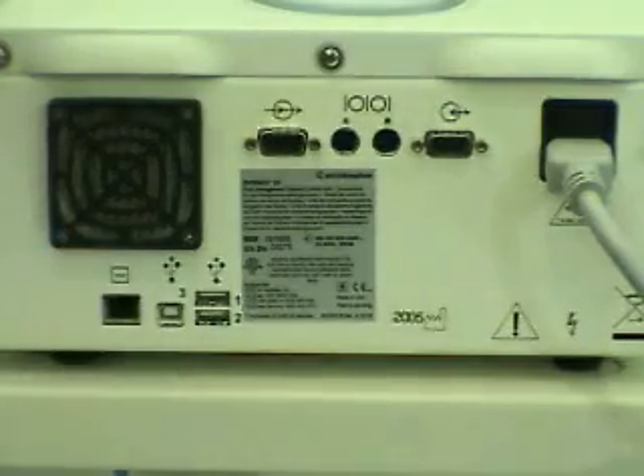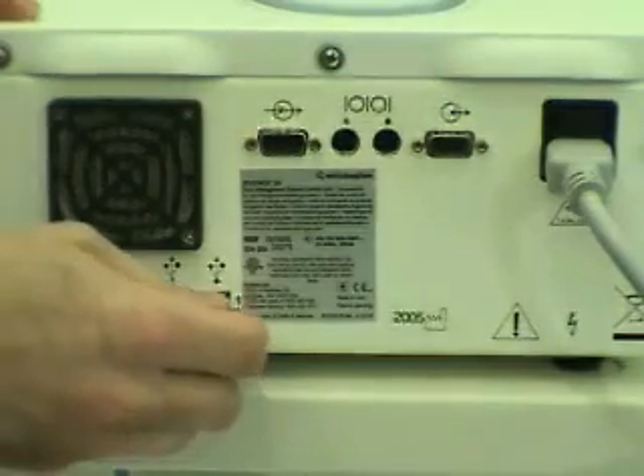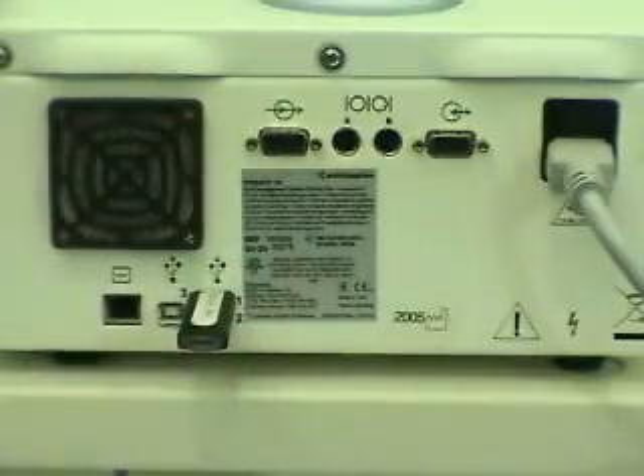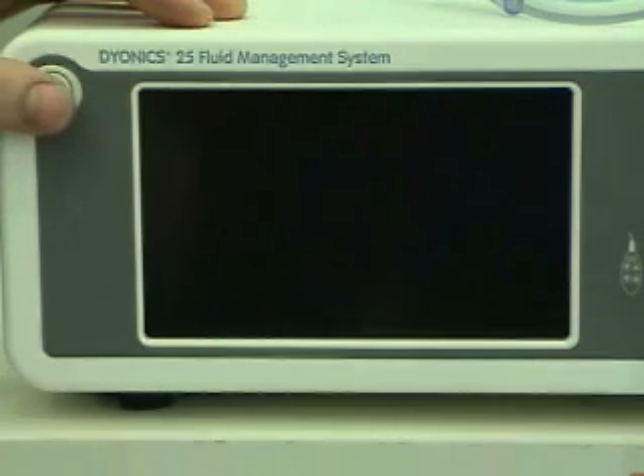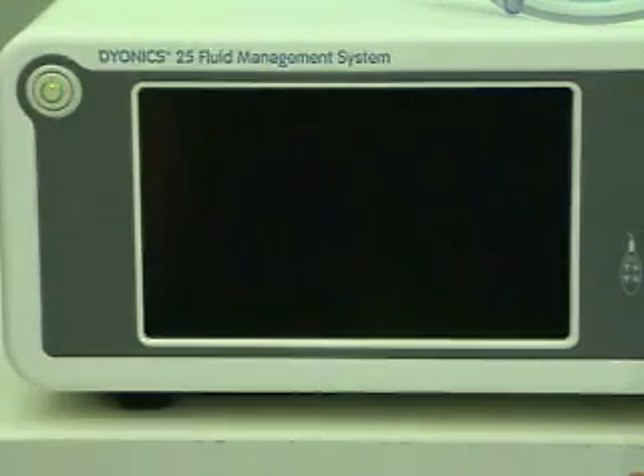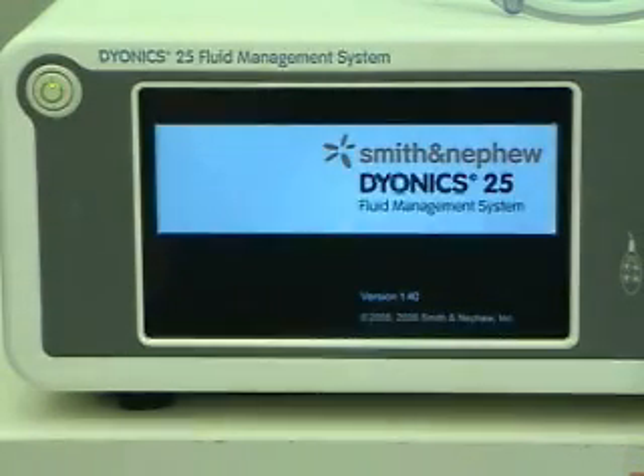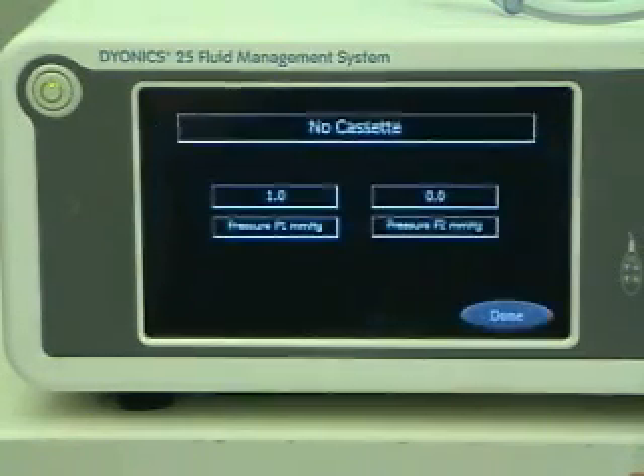So with the pump off, if you take the key and just simply insert it into the back of the pump. So you then turn on the pump using the power button. You get the normal splash screen as the pump boots up. And then instead of coming into the insert cassette screen, you get this Biomed test screen.